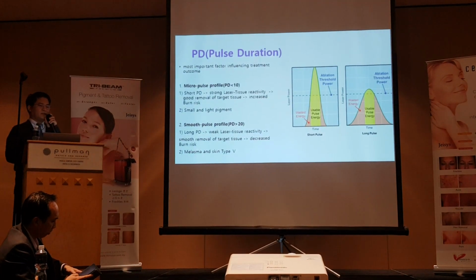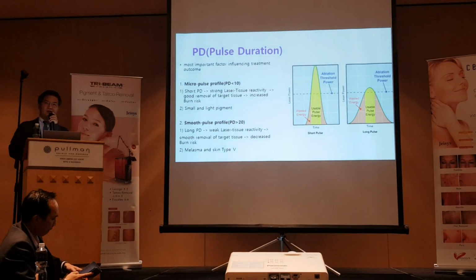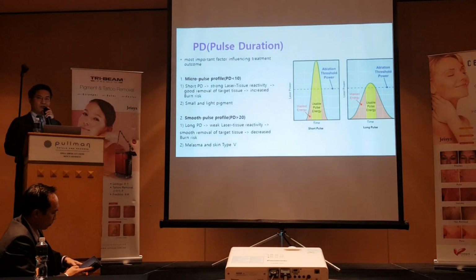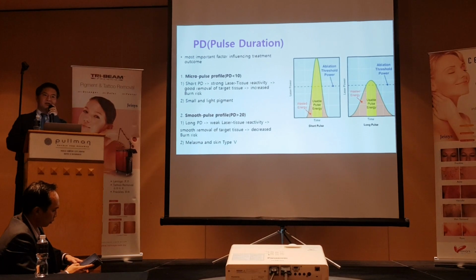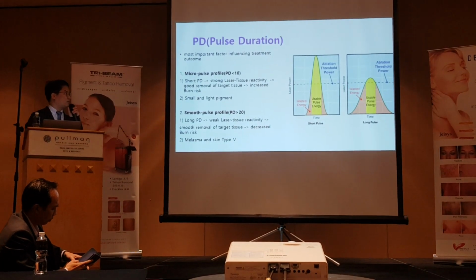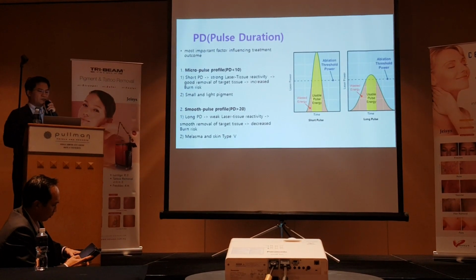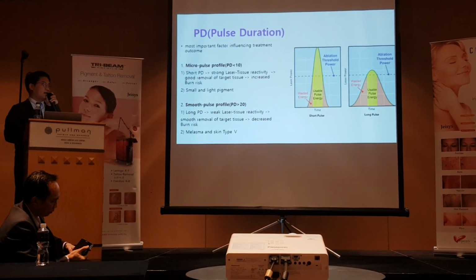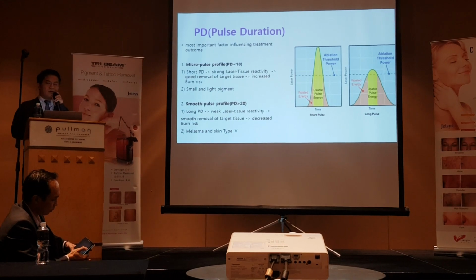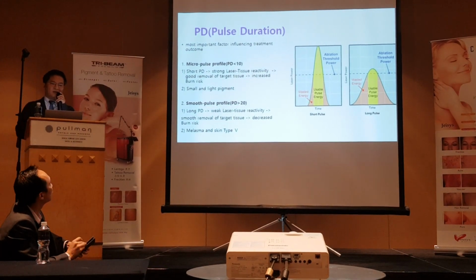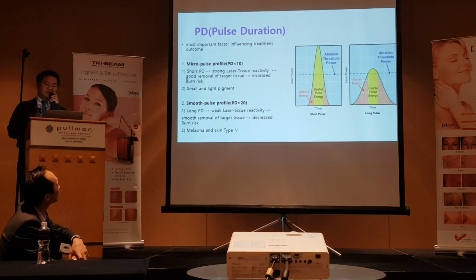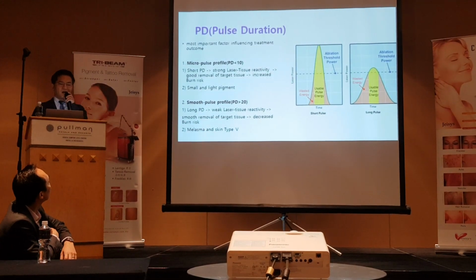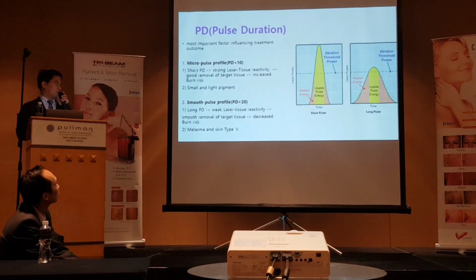Pulse duration is the most important factor influencing treatment outcome. First, the micropulse profile is a pulse duration less than 10 milliseconds. A short pulse duration makes strong laser tissue reactivity and good removal of target tissues, with increased burn risk. It is for small and light pigment removal.